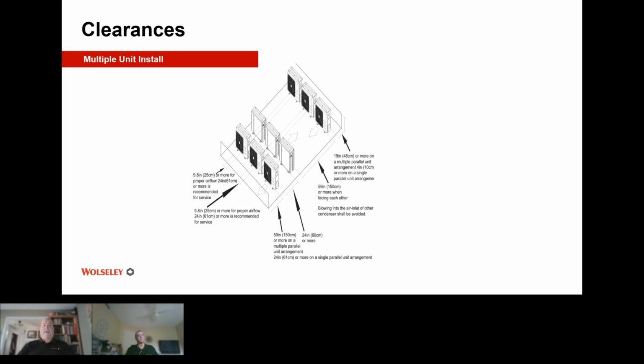Okay, so it is key to making sure that clearances, at least the minimums, are done, but there are good trade practices where we want to try and keep 5 feet from the facings, 24 inches from the sides, and 24 inches from back to back, so that they do not have to rob air from one other unit to get air for themselves. Okay, so minimum clearances must be followed.